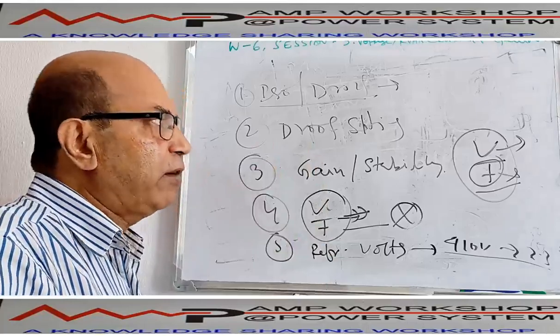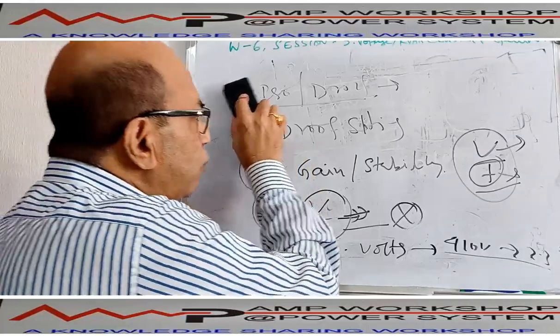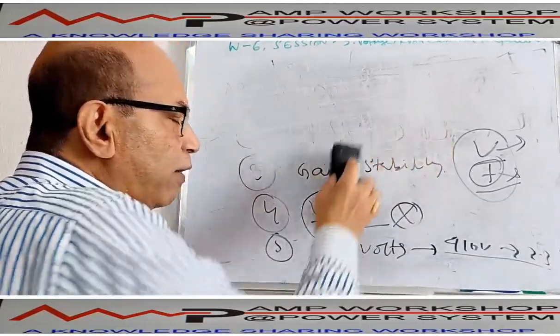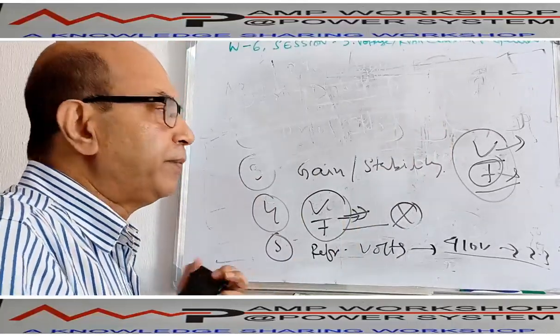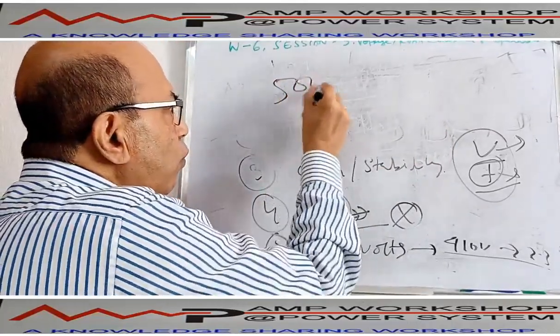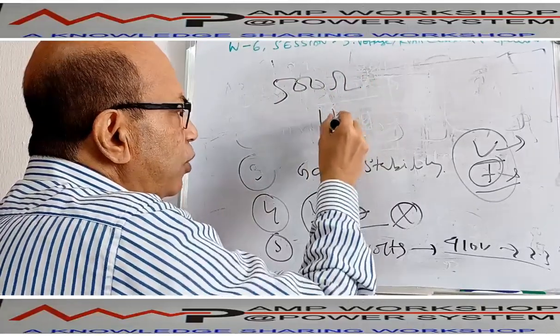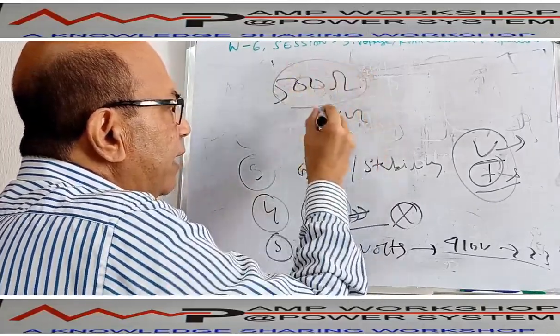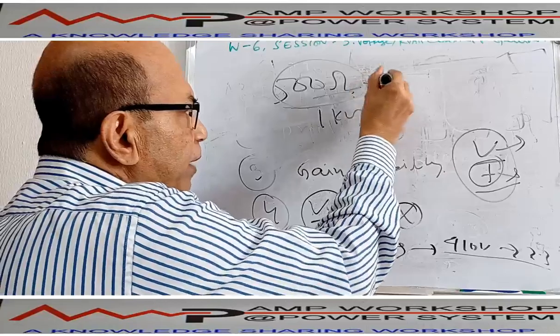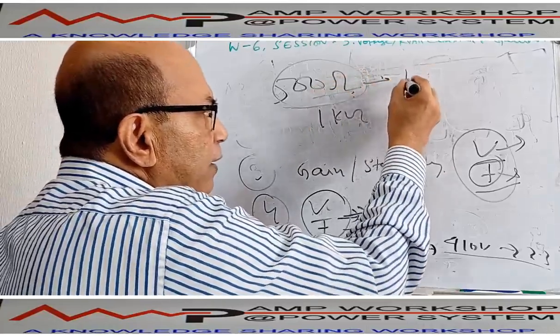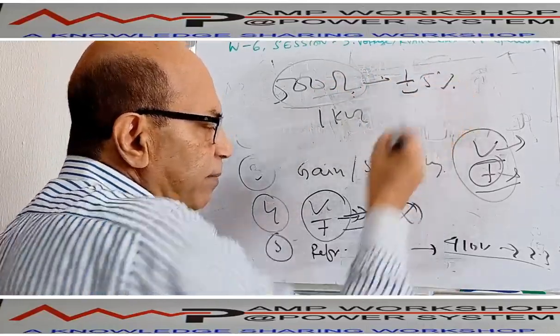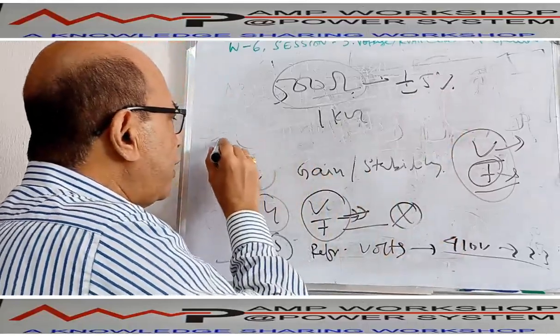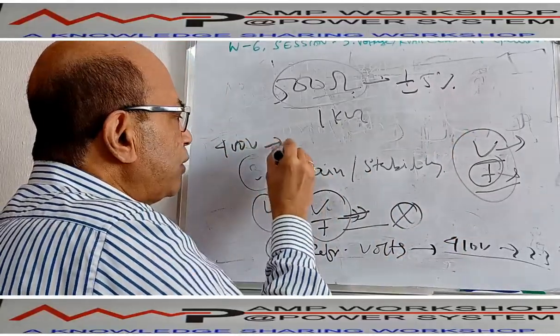So that variation we do by potentiometer. There are two potentiometers available. One is called the 500 ohm potentiometer, another is the 1K potentiometer. With the 500 ohm or the 1K potentiometer, we can change the voltage plus or minus 5% from the setting value. Suppose the setting value is 400 volt, which is equivalent to, suppose, 3.3 kV.